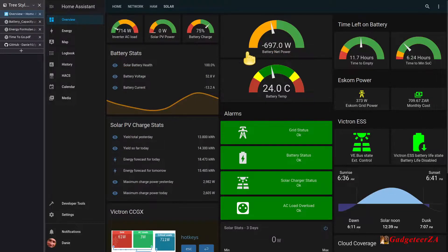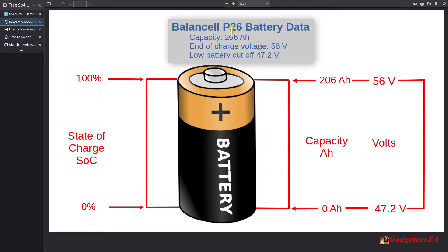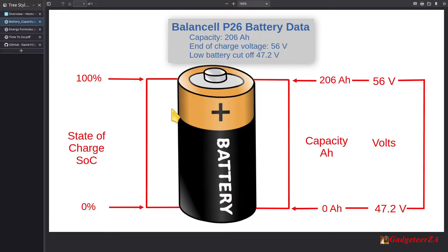I've got it set to 35 percent for my lithium phosphate — could have made it zero percent. I've got a Balance Cell P26 lithium phosphate battery made here in Cape Town, South Africa. The battery data sheet tells you the total capacity, in this case 206 amp hours at 52 volts average. Its end-of-charge voltage when full is 56 volts, and the low cutoff is 47.2 volts. State of charge ranges from zero when empty to 100 when full, and the capacity in amp hours scales accordingly.